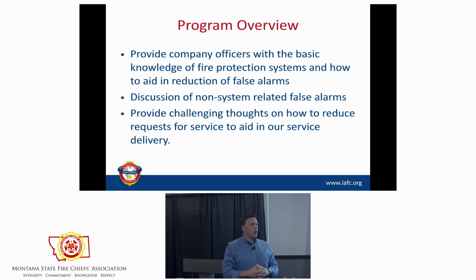Electric fire pumps get monitored for 3 conditions. Does anybody know what they are? Pump running, loss of power, and something called phase reversal on electric pumps. Diesels are a little different, but on the electric fire pumps, those are the 3 things. Now, why do we care about phase reversal? Well, what happens if the power reverses to an electric motor? It's going to go the other way. Is that a problem? Okay, so that's a good thing to monitor for.